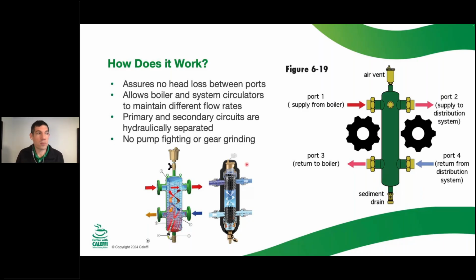One thing to mention here, and this comes up quite a bit, especially in a basics scenario, is pretty subtle, but you can see this is a darker red and this is kind of a pink, a little bit lighter shade of red. There is some temperature mixing that happens inside of a hydro separator, and I'll show you some of the flow scenarios in a couple of slides here. Their superpower is not ensuring a specific temperature. So if you need 140 degrees to go out to your system, it doesn't give you a specific number that you need on the input to ensure that.